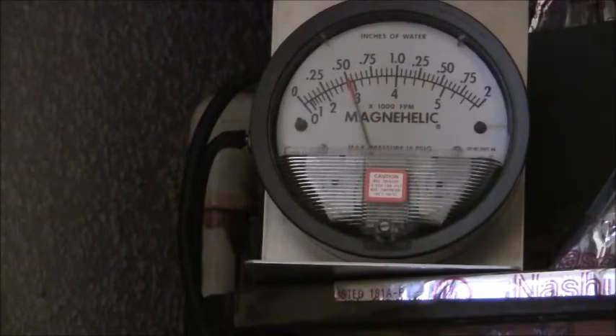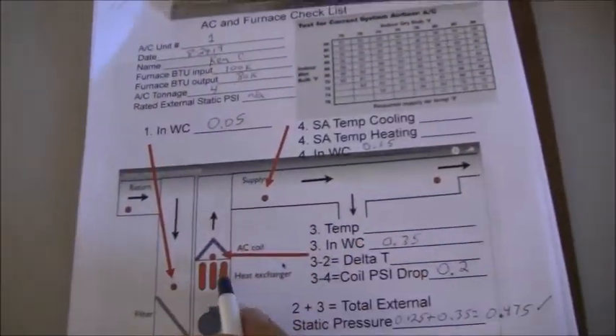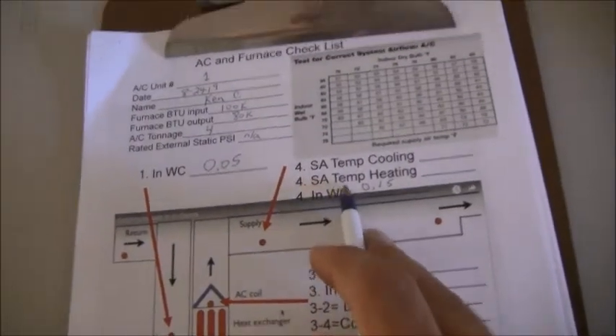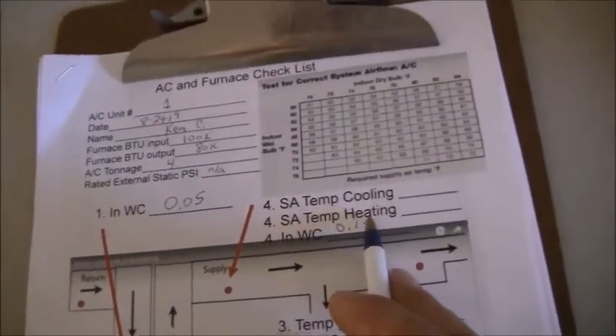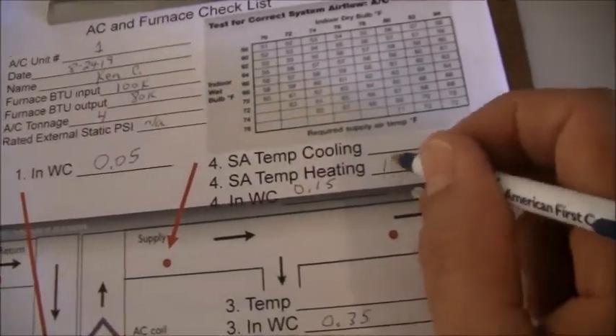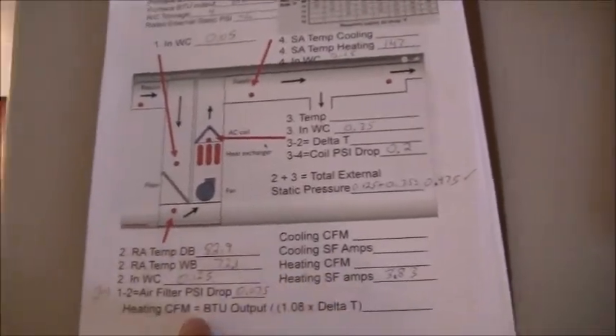Okay, so now that I know it's 147, I want to fill that out on my sheet right now. Let me see if there's any other information I need at the same time, but let's get that number. Alright, that temperature for the supply air heating temperature was 147. Alright, so we're going to leave that. And I got the amps there. I actually have all my information for the heating. I want to go shut the thermostat off because the house is already super hot. So let me go shut the thermostat off and let that shut off.